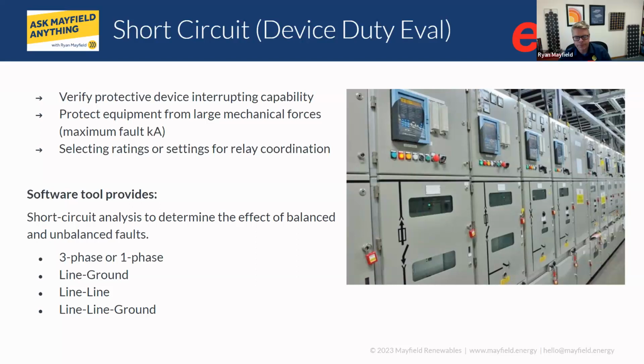Sure. Right, because the worst thing that could happen is you have an explosion, right? You have a fault, which is basically an electrical explosion. The equipment is not rated properly, and instead of the breaker tripping, it just melts, explodes, and somebody gets hurt. Then OSHA gets involved, and we want to stay away from that. So anytime it's a commercial, industrial, or renewable site, yeah, this would be a requirement. Okay, cool. Thank you.